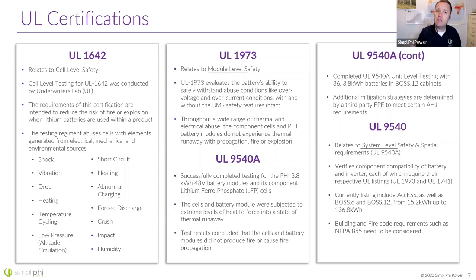If we succeed with that, we then have our UL 1642 and our UL 1973. To achieve UL 9540A, we take our UL 1973 battery modules and send them to a UL lab for a test. It's not a pass-fail test. Essentially what we do, and I'll show pictures of this in upcoming slides, is take one of the cells inside our battery module, wrap it with heating wraps, and heat it to the point that it goes into thermal runaway.